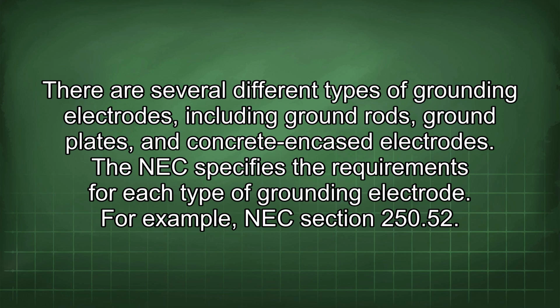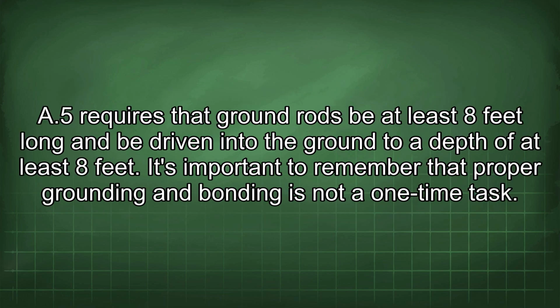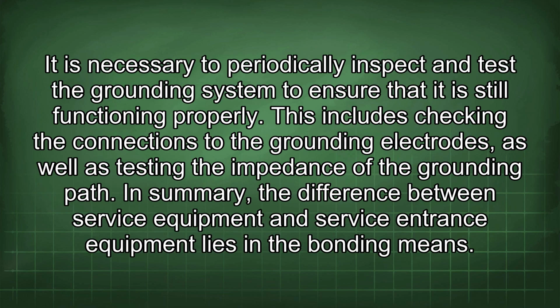For example, NEC section 250.52(A)(5) requires that ground rods be at least 8 feet long and be driven into the ground to a depth of at least 8 feet. It's important to remember that proper grounding and bonding is not a one-time task. It is necessary to periodically inspect and test the grounding system to ensure that it is still functioning properly. This includes checking the connections to the grounding electrodes, as well as testing the impedance of the grounding path.